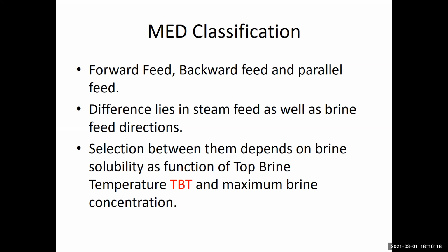So we have the forward feed, it's going from left to right, or actually it is going in the same direction of the vapor. And you will see that in the figure. Backward, which is the opposite, or parallel, which is basically going perpendicular to the direction of vapor flow. This nomenclature is related to how the vapor and the seawater flowing directions are going to be the same, opposite, or normal when you look at the system.